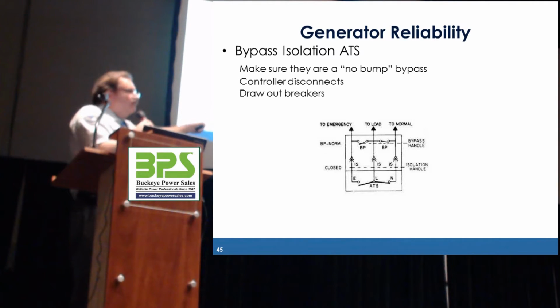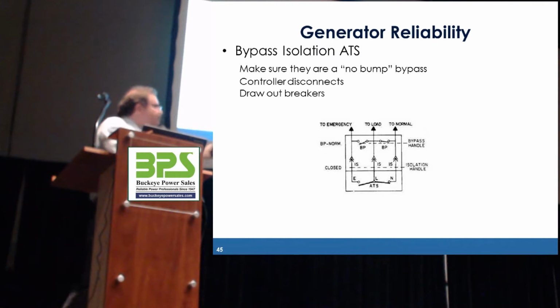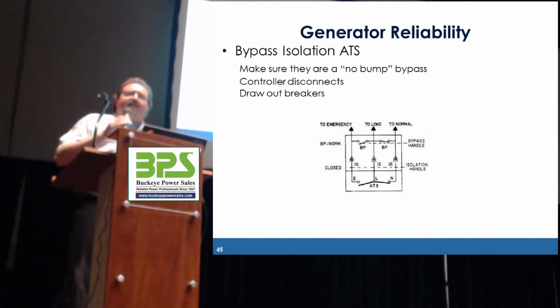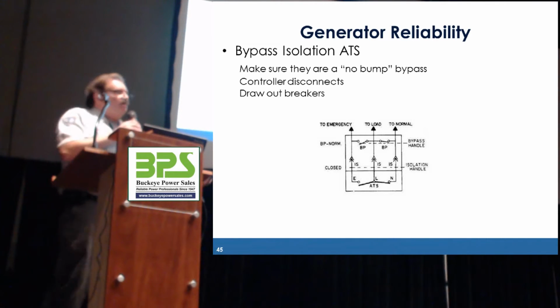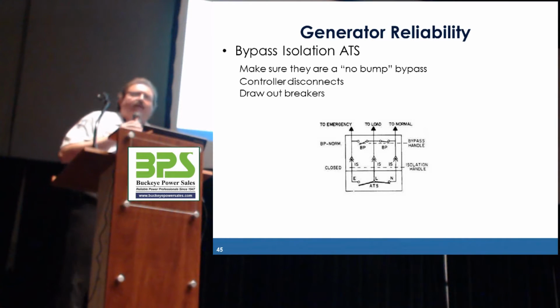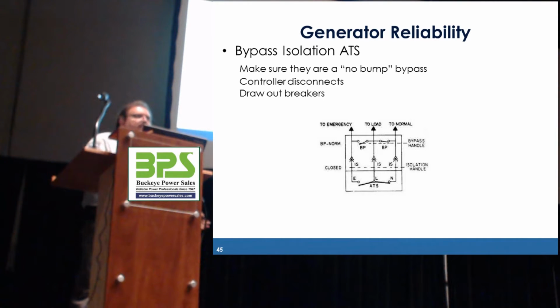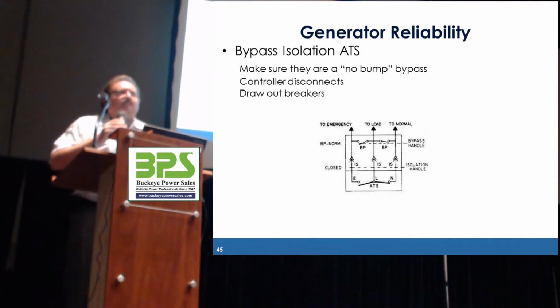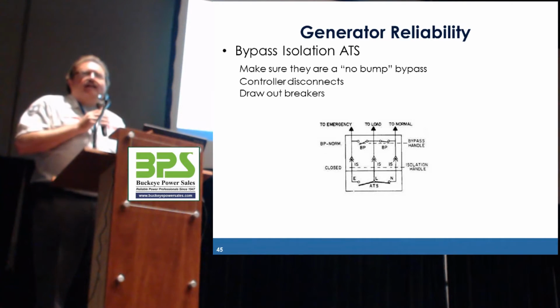It doesn't affect the load whatsoever, and then we can put it back in, unbypass it, and it goes back to normal. The other advantage of a bypass isolation switch is if the contactor itself needs service, you can put it to the maintenance bypass, draw that contactor out, do all the work that needs to be done, but the facility never had an interruption.